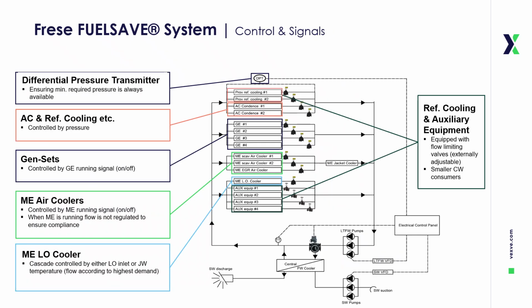The Frese FuelSave system integrates advanced control algorithms with continuous monitoring of cooling water circuits. Sensors track key operational parameters such as flow rate, differential pressure, and temperature. These inputs feed into the FuelSave controller, which calculates the optimal balance point in real time.